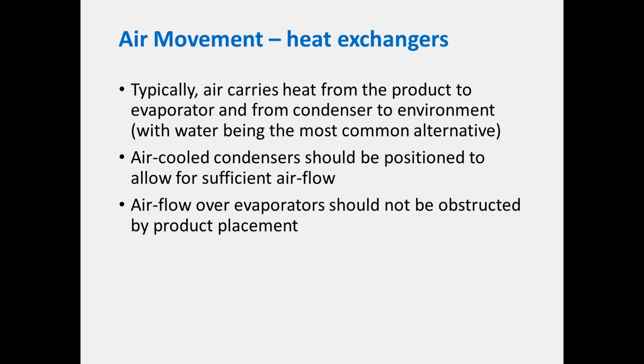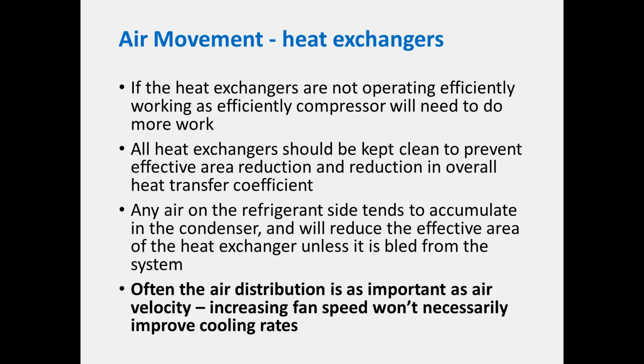They need to be free from obstruction. If your heat exchangers are partially blocked, their effective area is reduced. For example, if your evaporator isn't using all its heat transfer area, the compressor will start to have a lower suction pressure and a higher duty as a result.